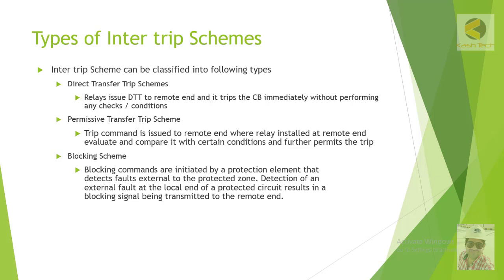So there are three types of basic protection schemes. In the Direct Transfer Trip scheme, the relay at one end — for example, Station A — sends a trip command to Station B at the remote end, and the remote end trips immediately without making any logical decision or evaluating any local conditions.